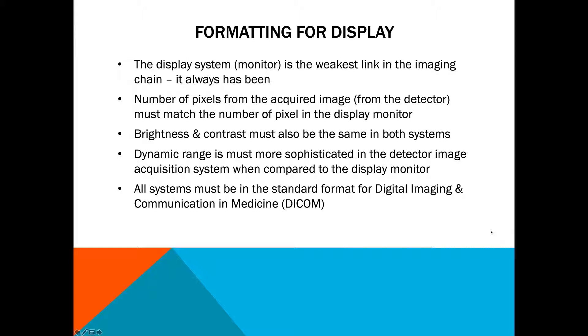When formatting for display, the computer is doing everything. What you need to know is that the monitor is the weakest link in the imaging chain — it has always been the weakest link, while our detectors are very sophisticated acquisition components. The number of pixels from the acquired image must match the number of pixels in the display monitor. The brightness and contrast must also be the same in both systems, and the dynamic range must be more sophisticated in the detector image so that you can manipulate the windowing and leveling. All of this is happening behind the scenes as a pre-processing operation.